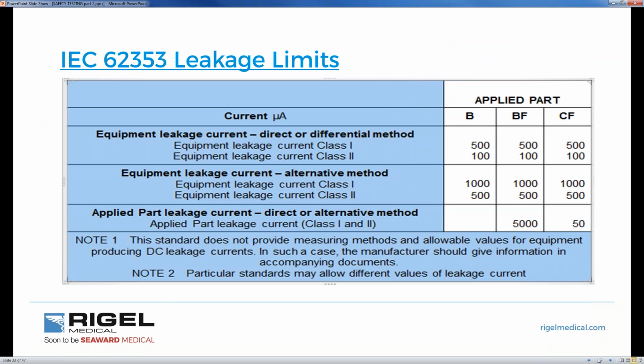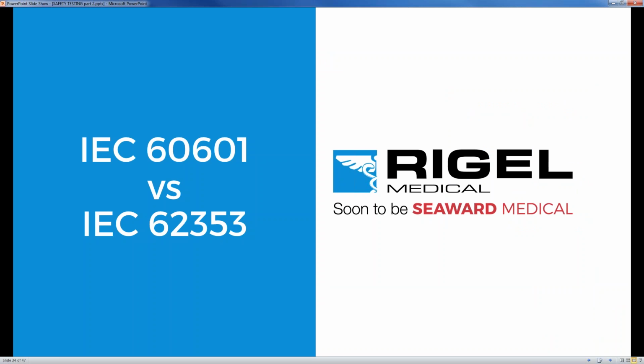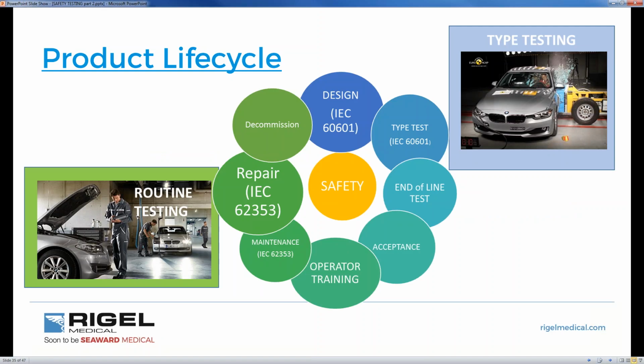Here are the pass-fail thresholds for 62353. You'll notice that they're very different from our 60601. So we're going to have a look at what the differences are between using 62353 and using 601. Where are the benefits? What's the difference? Why is it applicable? Well, your 60601 is very much like our type test. It's very much like our crash test dummy. It is used in the design phase and at the end of line in a production environment.